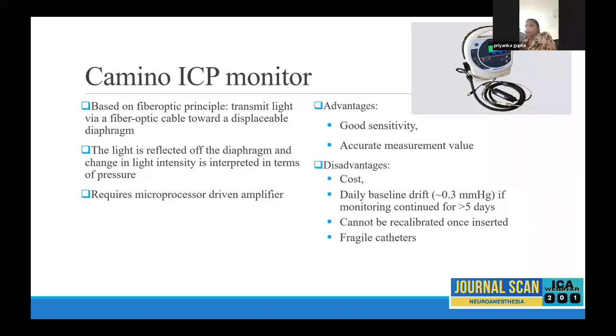The light is transmitted and falls on a displaceable diaphragm or mirror. When there is some intracranial pressure, the diaphragm is displaced with the pressure. So light is reflected off the diaphragm and the light intensity changes. That change in light intensity is interpreted in terms of pressure, so the greater the change in light intensity, the higher the intracranial pressure. And because these are small values, they need an amplifier also.